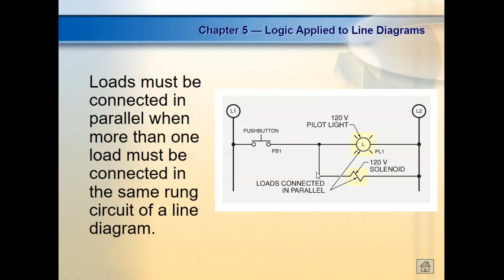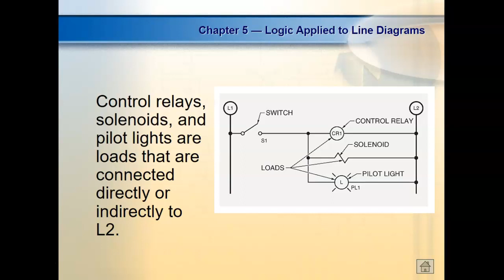So control relays, solenoids, and pilot lights are loads that should be connected to your neutral side. One is hot, two is neutral, and everything's connected between them. And since they're loads, they should never be connected in series.